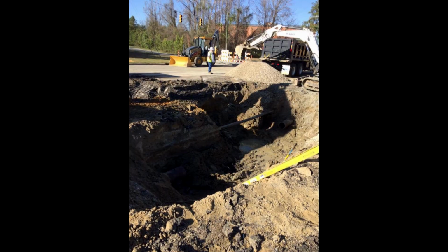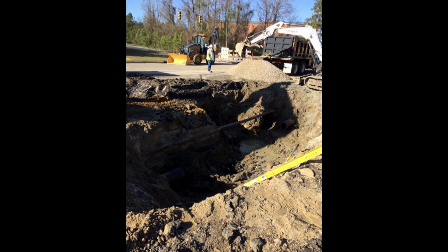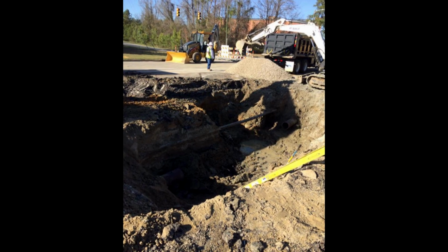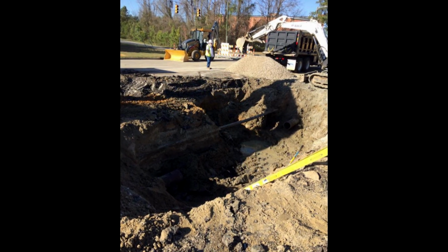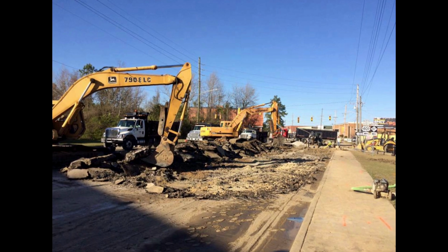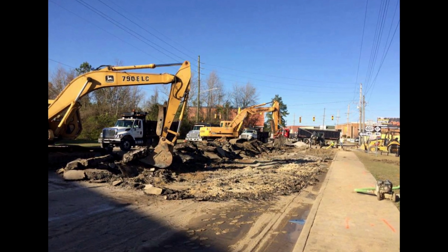A boil water advisory would be issued if we have a main break and we lose system pressure. That means the system pressure has gone below 20 psi, and you can have contaminants that are flushed back into the water pipe. The primary reason for the boil water advisory is main breaks due to construction, or we have a hurricane and we have flooding, we have main breaks, and we lose system pressure.